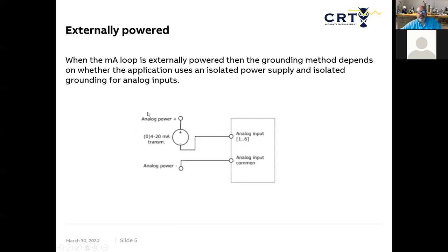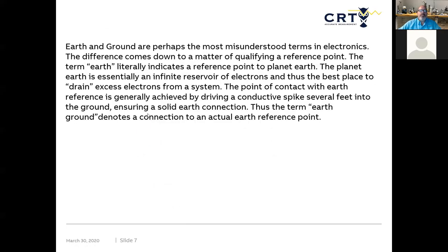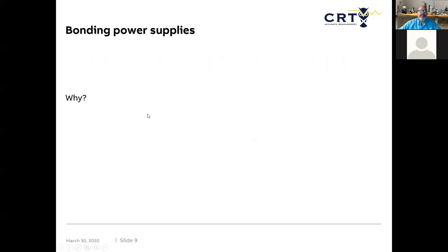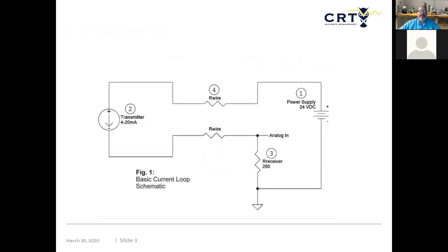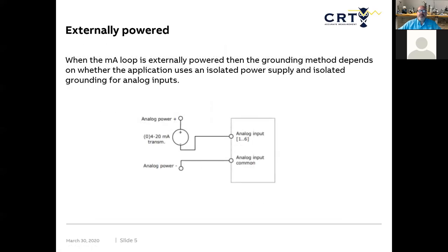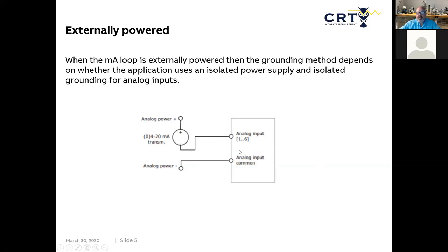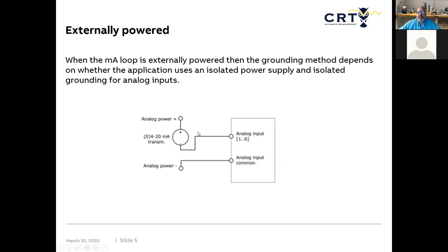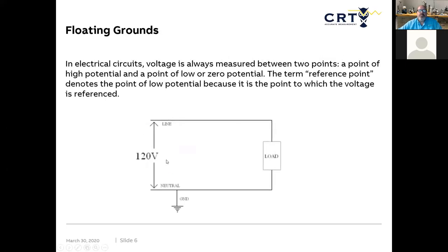What happens if I have a transmitter where the power is coming from an external device? I've got 24 volts coming off a power supply. I'm going through the transmitter, and then coming into an analog input on my device. But I still have to make sure that that analog input common is then referenced to the analog power supply. So it's very important that I basically bond these together, my commons, or else I won't be able to measure anything.